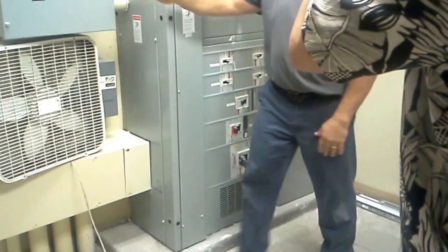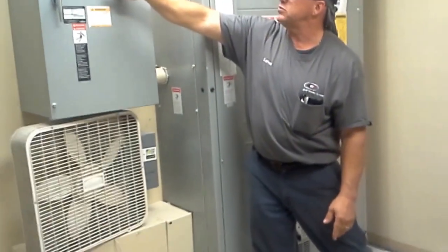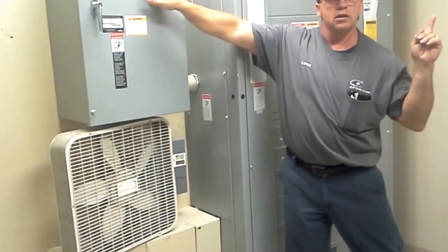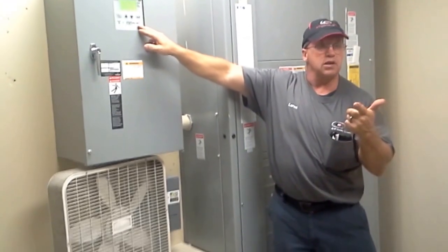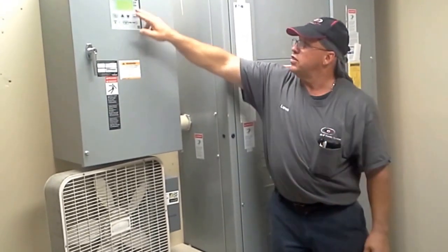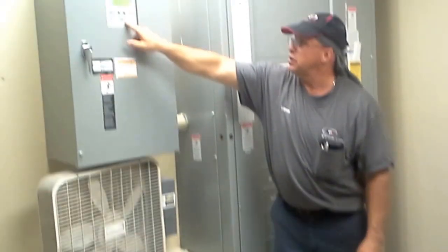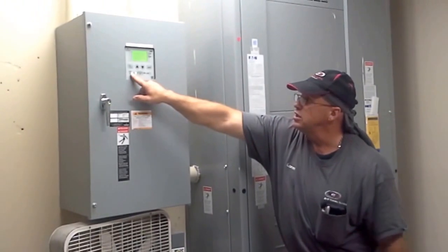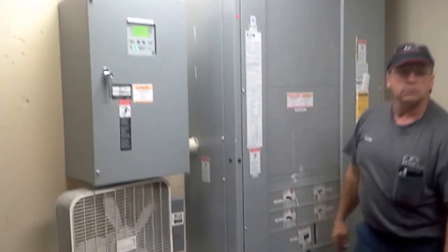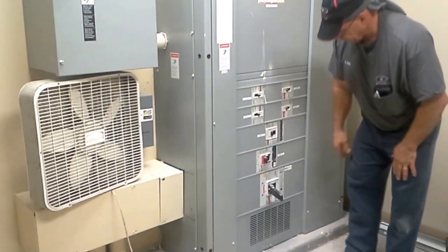So with that said, I'm going to go ahead. Yeah, go ahead. This is going to simulate you lost your utility, right? And the main thing to look at is here. Watch how fast this light comes on. When that thing comes up to speed, which creates your hertz, 60 hertz, 60 frequency, and 208 volts, this thing will monitor it. As soon as it's there, it's going to switch from here to here. But when I kill this switch down here to simulate a power loss, that light's going to go off. All right? And the room is going to go dark too. All right. That's good. Okay, here we go.